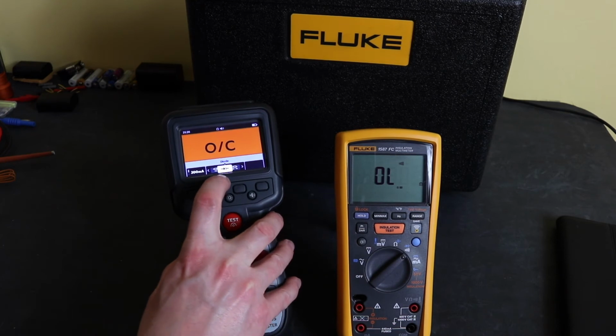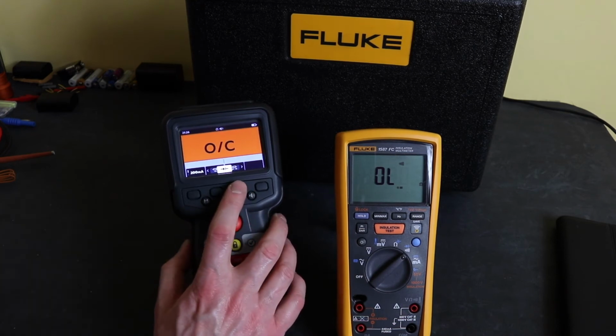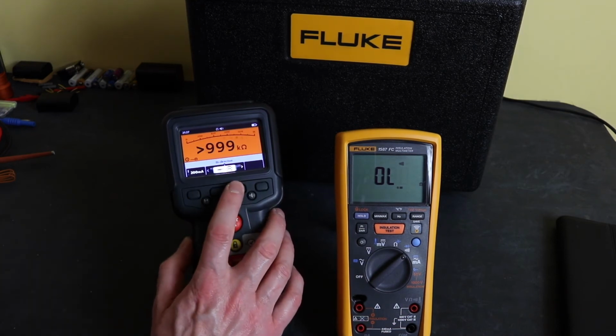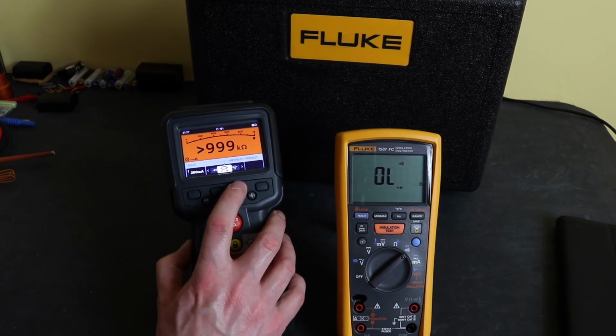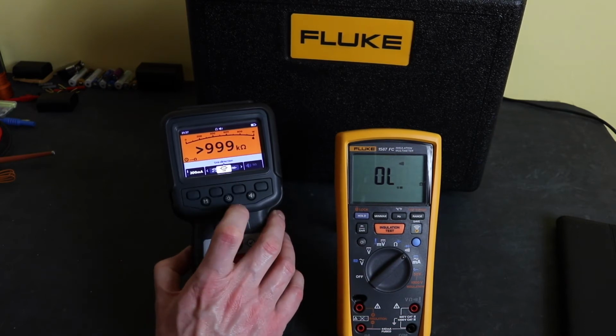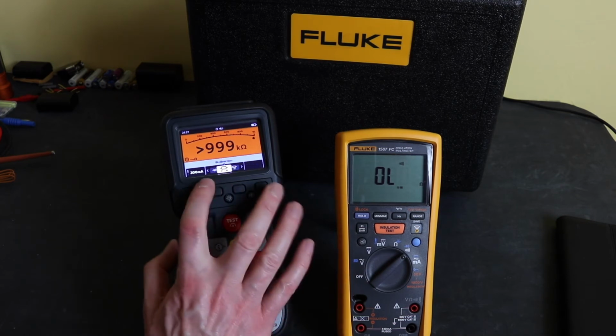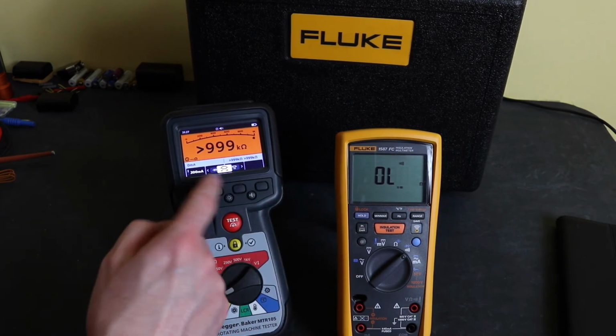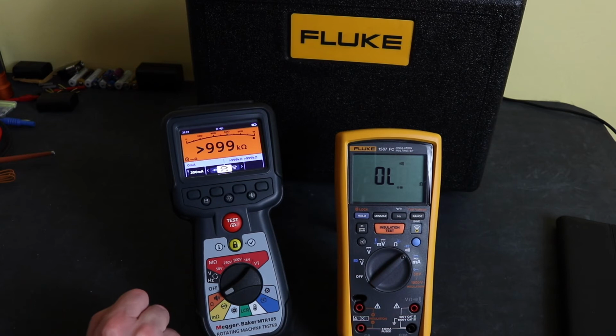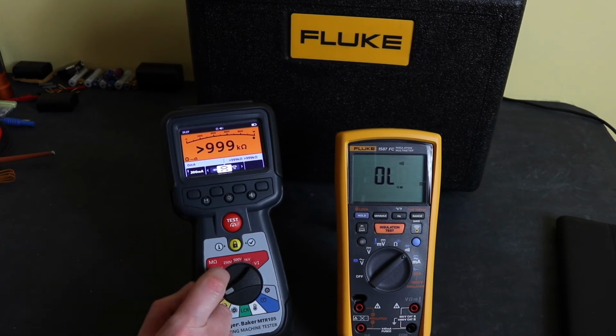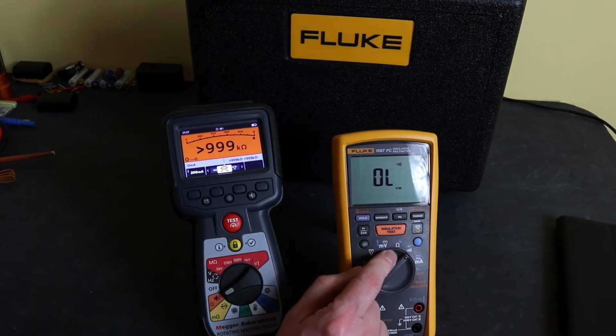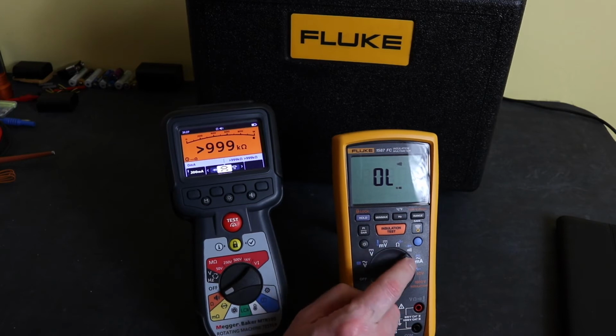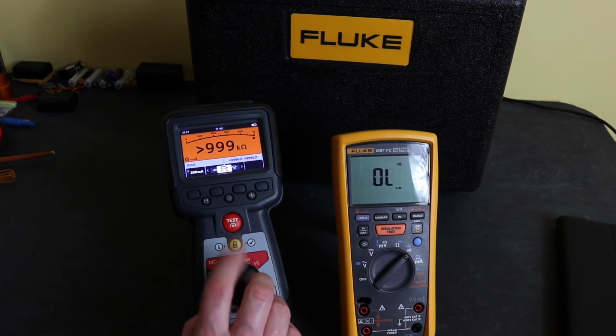Yeah, so this does have a diode test as well. And with continuity and resistance, you also have a bidirectional test or a unidirectional test. On the bidirectional, the instrument will do one test one way, flip the leads and do a second test and then give you the average. This just gives you the unidirectional test for the ohms and for continuity.